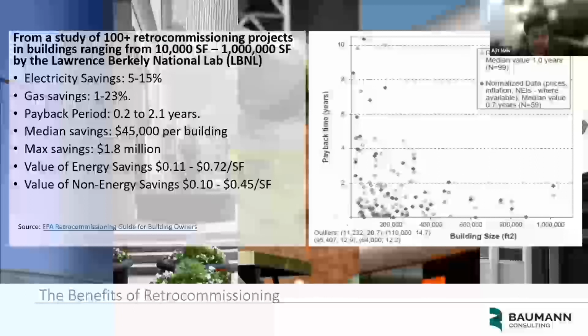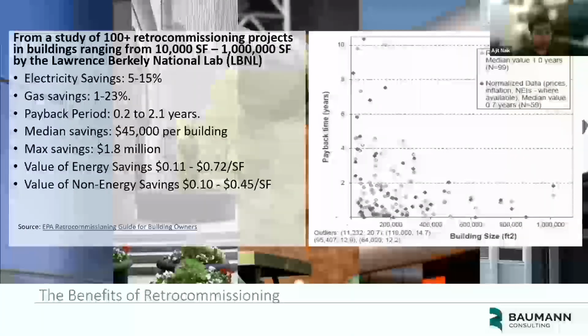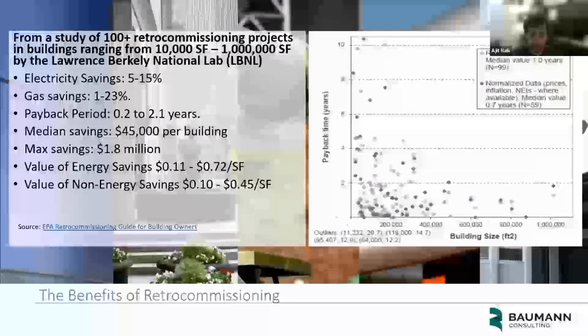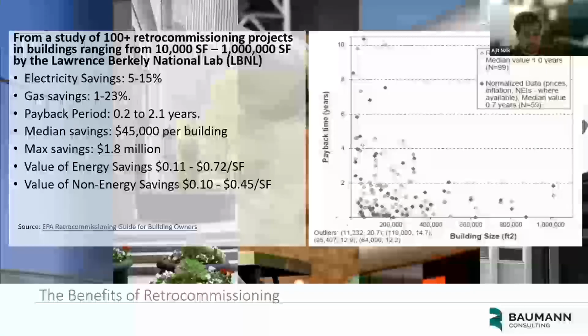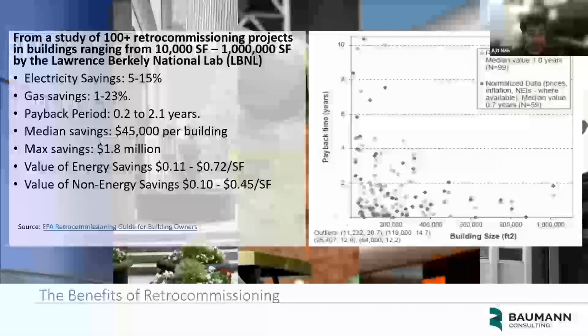Generally, retro commissioning has a lot of benefits. So rather than looking at our own anecdotes, we looked at some studies done by the Lawrence Berkeley National Laboratory in California, which is really the country's foremost expert on retro commissioning. They did a study a few years ago of over 100 retro commissioning projects, ranging from 10,000 to 1 million square feet, all commercial properties, and did a deep dive into how much these buildings typically saved. These buildings ranged in electricity savings from 5 to 15%, gas savings from 1 to 23%. The overall retro commissioning efforts had a very short payback period of, on average, 0.2 to 2.1 years.